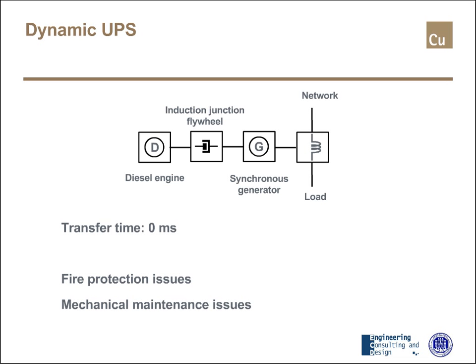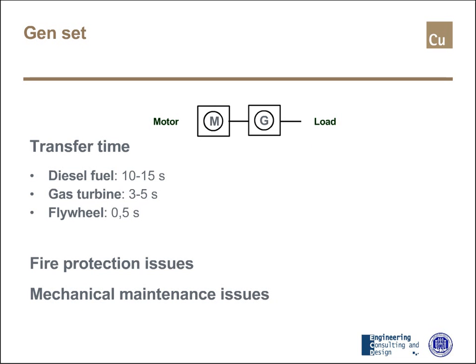However, a dynamic UPS is mechanical equipment, so the designer must face not only electrical issues but also fire protection and mechanical issues, including maintenance. More or less the same applies to a genset, where energy is provided mechanically by a motor supplying a generator coupled with the load. But in this case the transfer time is not zero — it is quite large, from 10–15 seconds for diesel fuel to half a second for flywheel. In any case, gensets introduce fire protection and mechanical issues.